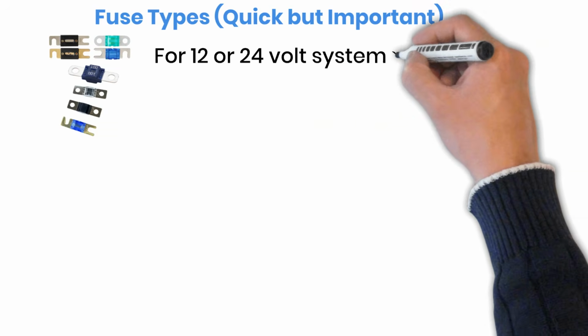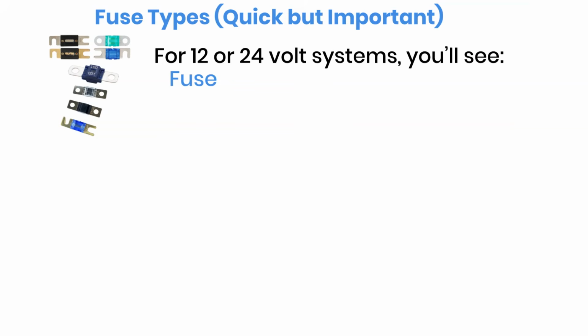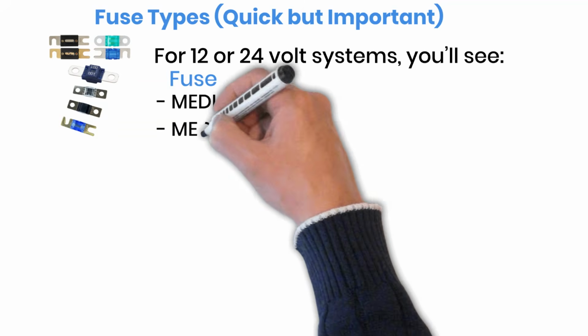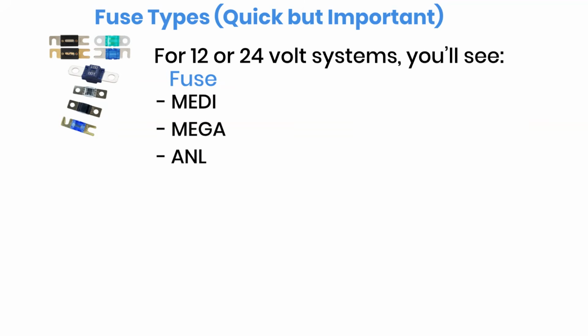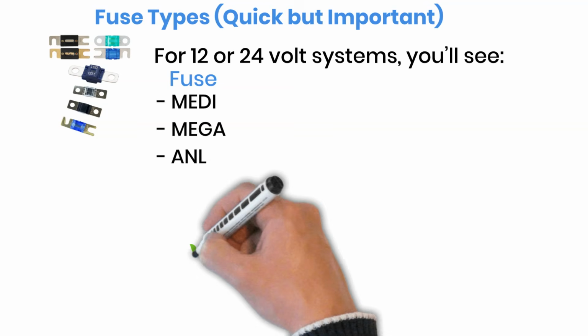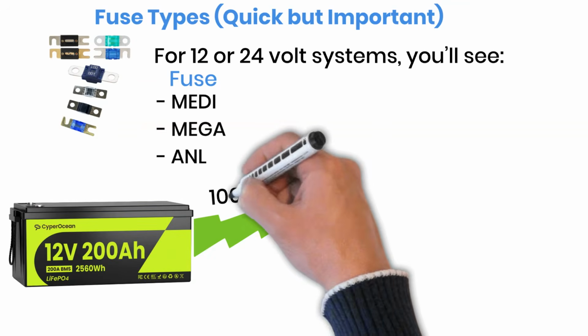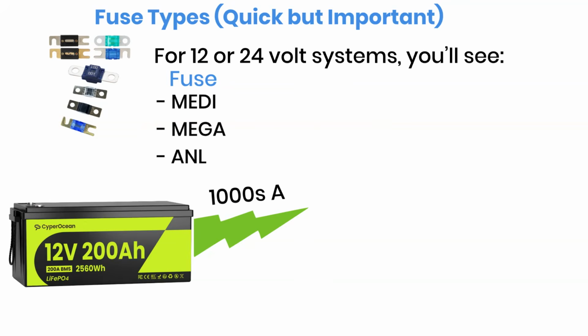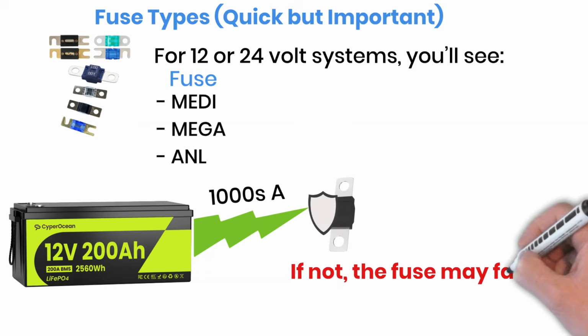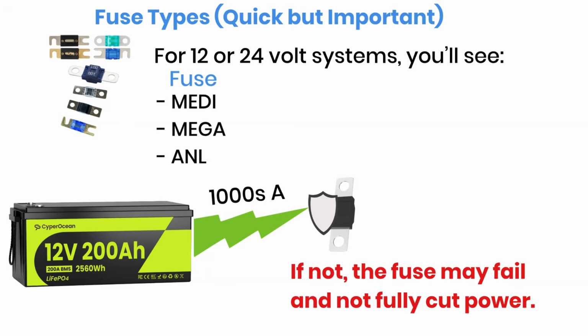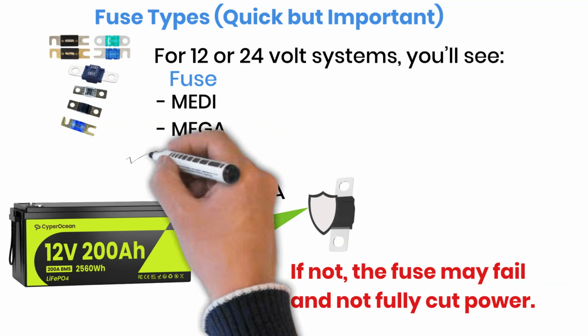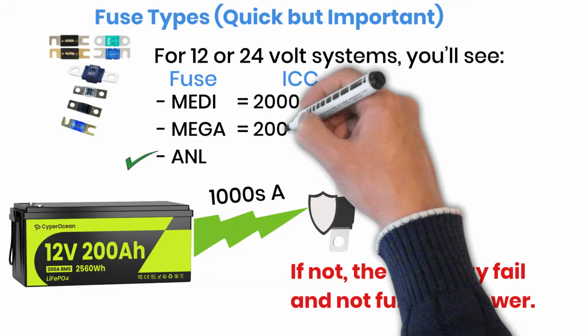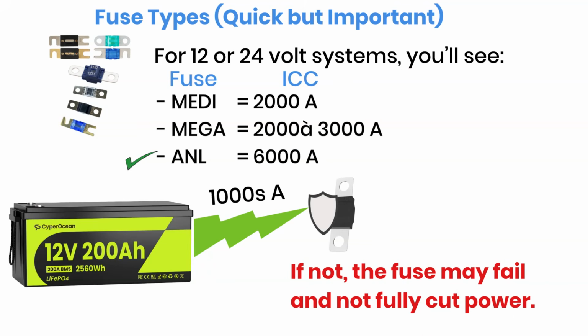Now let's talk about fuse types. Not all fuses are the same. For low-voltage systems like 12-volt or 24-volt, you'll see types like MIDI, Mega, and ANL. All can work, but there's one thing most people ignore. Lithium batteries can dump huge current instantly. In a short circuit, it can go into thousands of amps. So your fuse must be able to stop that surge safely. If not, the fuse can fail badly. Sometimes it doesn't fully break the circuit. That's why many people prefer ANL fuses. They usually have a higher breaking capacity, which makes them safer for lithium setups.